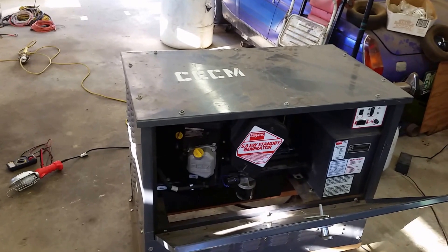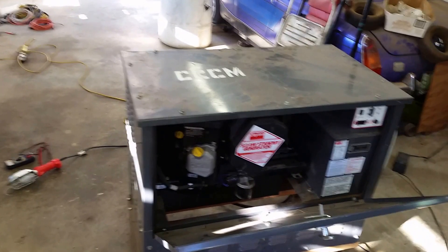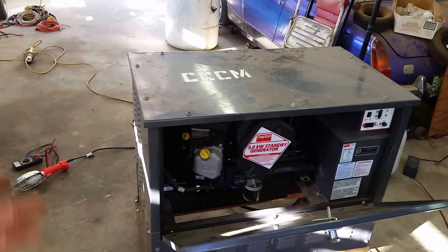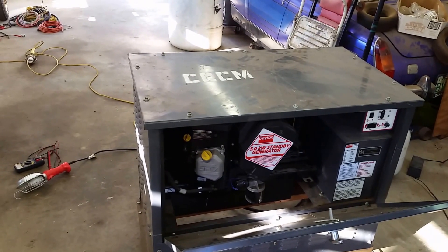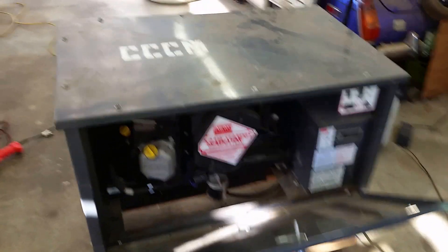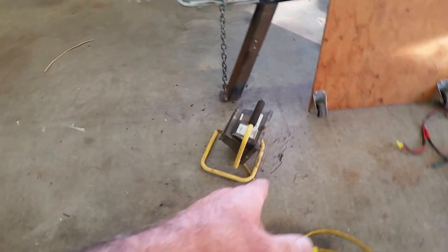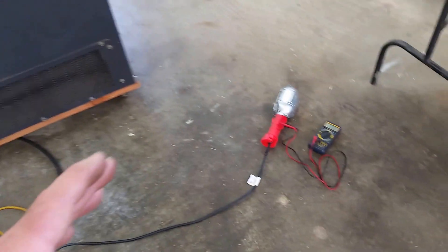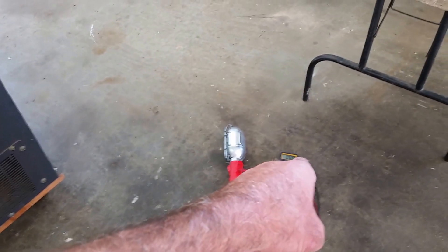I got the voltage adjusted right and everything was good, but I really wasn't confident that I had the hertz set. It's a new generator that was installed once but never used, so all I had to go by is how it was set up previously.